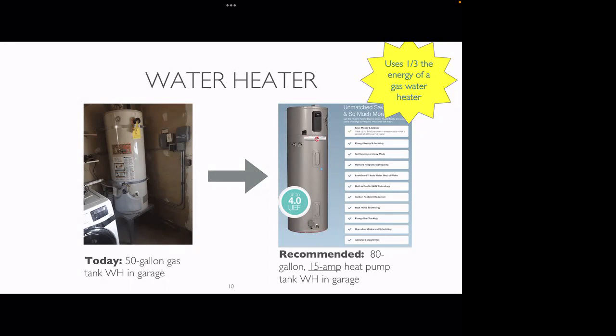Even though it may feel cool in your garage, there's actually quite a bit of heat there that can be gathered, sort of like a sponge. So the heat pump water heater we're recommending here is a Rheem 80-gallon, 15-amp heat pump water heater. We really like the 15-amp water heaters as opposed to the 30-amp water heaters. Rheem makes both because it fits better on the panel. The fewer amps you can use, the better.